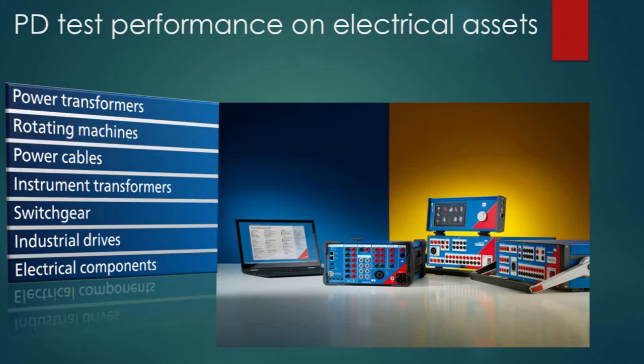The insulation is normally made of a dielectric material, typically polymeric materials. Repetition of PD activity at a defect site may cause insulation breakdown when the defect grows until it bridges the electrodes across the insulation. Consequently, breakdown of the whole cable will occur, and at the final stage, the cable insulation destruction will be visible to the naked eye.